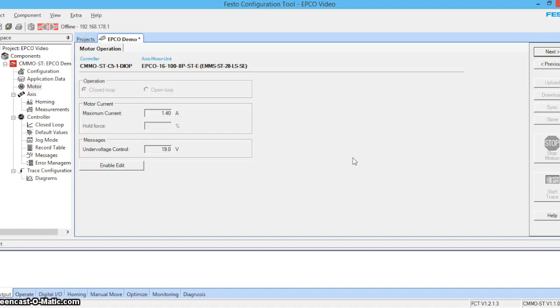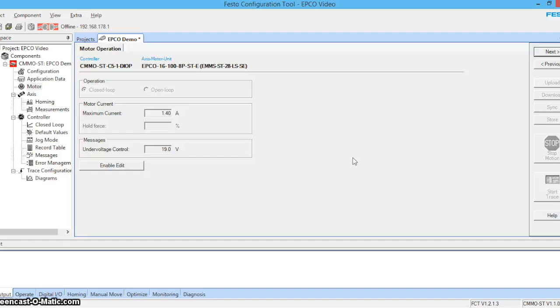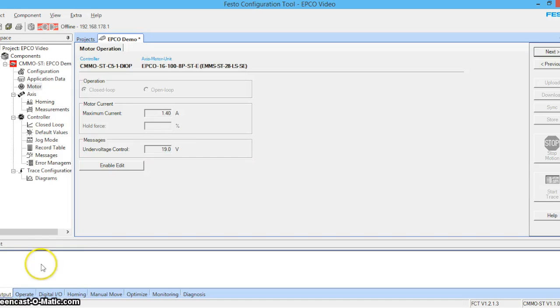Here you can see that the FCT automatically selects the maximum motor current based on the motor and actuator configuration. The FCT also automatically selects the undervoltage level. If the intermediate circuit voltage in the drive drops below this value, for example, if the power supply is not functioning correctly, then an error will occur.